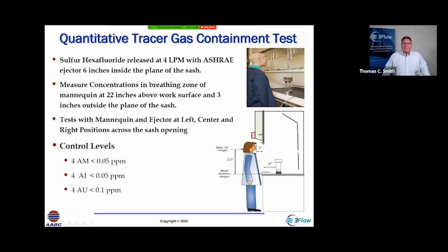Now we move that mannequin from left, center, and right side of the hood, and we use the average 5-minute concentration as our control level. So for an as manufactured test, we generally accept 0.05 parts per million as an average in the breathing zone. For an as installed or as used test, we might allow it to go up to 0.1 parts per million. But that's a pretty low concentration. That's 100 parts per billion from a containment criteria. So all of these factors have to be carefully installed and adjusted in order to achieve this level of performance.